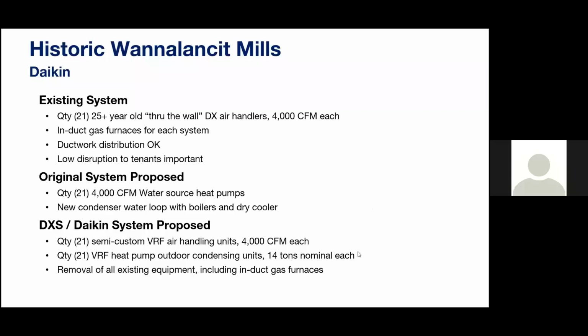So the question might come up about why we did not just use simple single or two-stage condensing units as opposed to VRF. But as we've already spoken about all the efficiency benefits of VRF, along with the low ambient heating capabilities, that made VRF really the go-to system for this one. And then also the Historic Association didn't want anything too tall obstructing the view at the top of the building, which as you can see by that Christmas light picture, we try to keep clear. And comparing the height of a cooling tower versus VRF condensing units, the VRF condensing units would be much smaller, which was another reason to push the VRF route here.